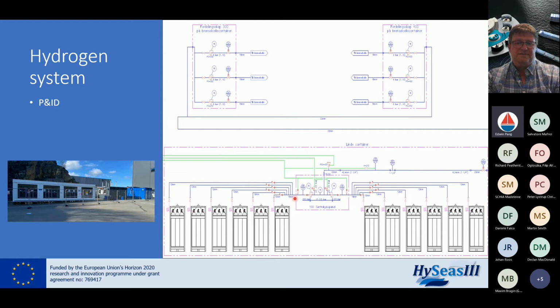Inside this hydrogen storage we also have included some one-directional valves to make sure that in case of a leakage, only one of these packages is actually leaking and not all of them. We also have some valves to shut down through the emergency system, and also manual valves to shut down and to bleed out if we need to do some kind of maintenance on the system.